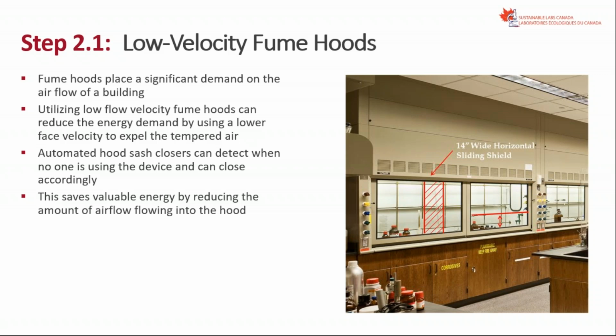Now, in addition to that, we can have other strategies like hood sash closure that can reduce the energy as well. Now, if we're going to be looking at other approaches which are being implemented in Europe or in Asia, there are some fume hoods which are considered operationally safe with 40 feet per minute, which means a 60% reduction.